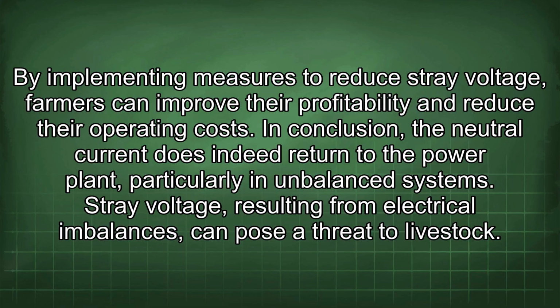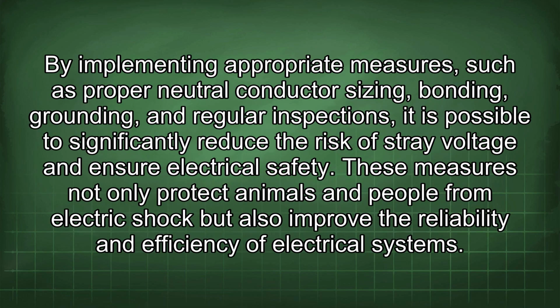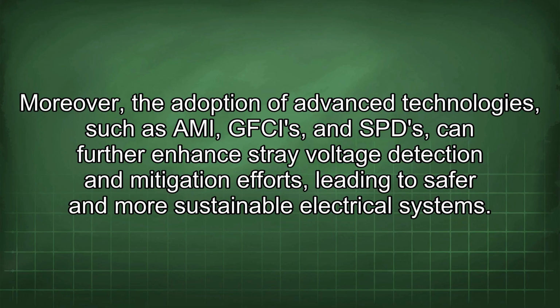In conclusion, the neutral current does indeed return to the power plant, particularly in unbalanced systems. Stray voltage resulting from electrical imbalances can pose a threat to livestock. By implementing appropriate measures, such as proper neutral conductor sizing, bonding, grounding, and regular inspections, it is possible to significantly reduce the risk of stray voltage and ensure electrical safety. These measures not only protect animals and people from electric shock, but also improve the reliability and efficiency of electrical systems. Moreover, the adoption of advanced technologies such as AMI, GFCIs, and SPDs can further enhance stray voltage detection and mitigation efforts, leading to safer and more sustainable electrical systems.